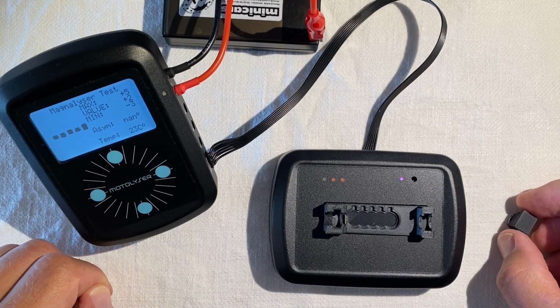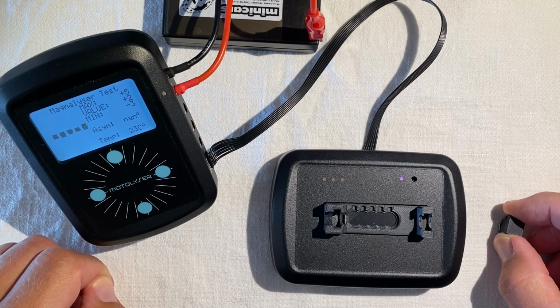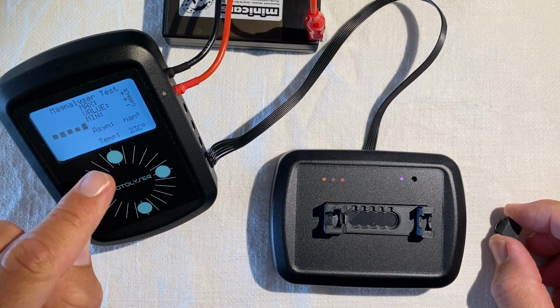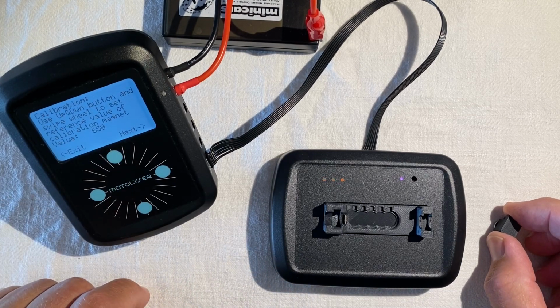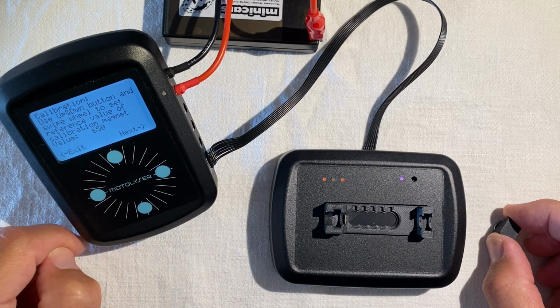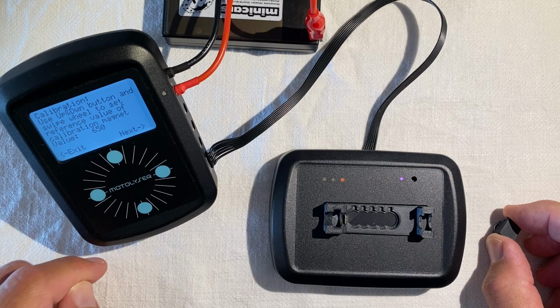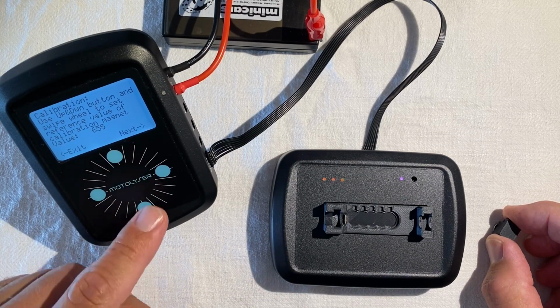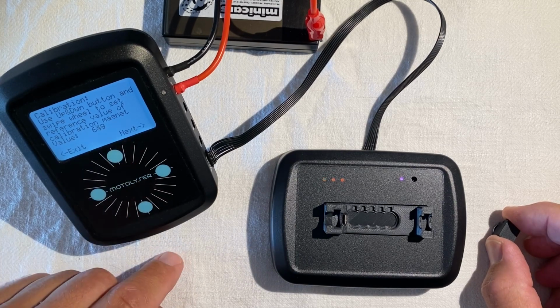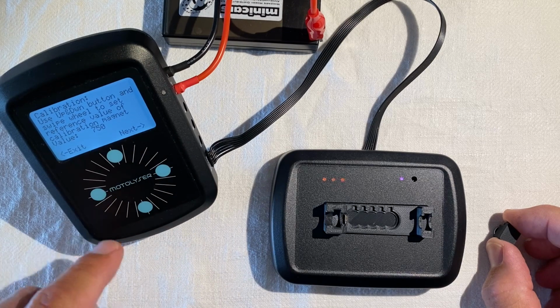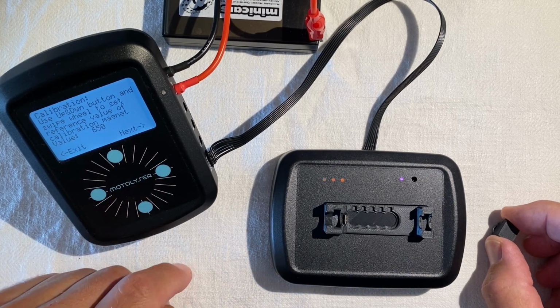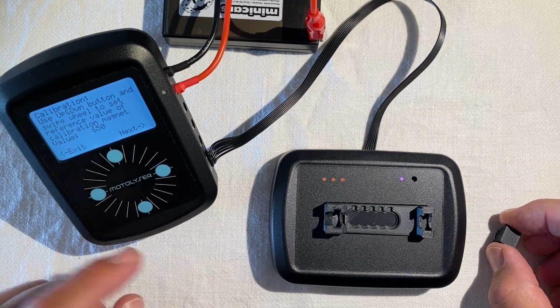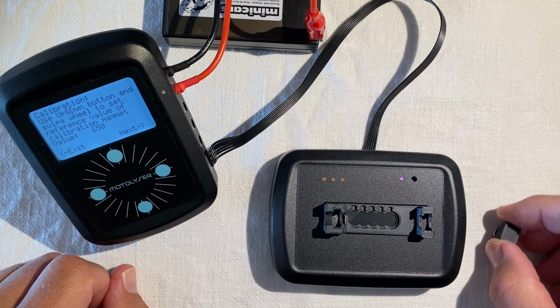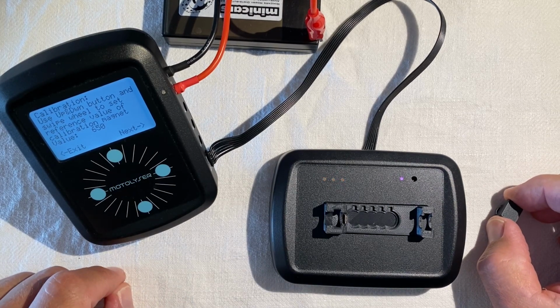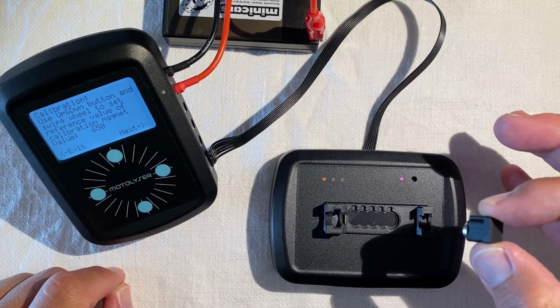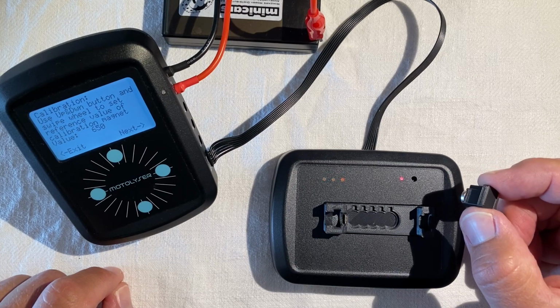The first time you use your Magnalyser, you need to make sure to calibrate the sensors to your Magnalyser. That's done by clicking the up button to enter the calibration mode. And here you have a calibration magnet reference value, which is defaulted to 650 in this case. You can increase that value by up button or decrease it by the down button. You can also make bigger steps by swiping clockwise and counterclockwise. This is in order for you to be able to adjust the amplification in the system to adapt to whatever values you are used to. 650 is our default, and then depending on the magnet that we use for calibration, it can go up and down. So let's start the calibration.